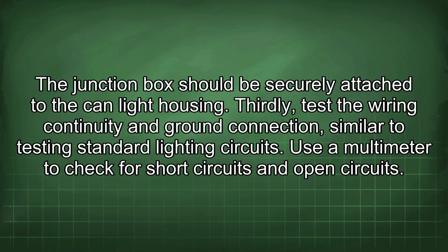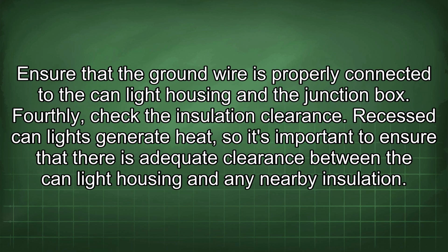Thirdly, test the wiring continuity and ground connection, similar to testing standard lighting circuits. Use a multimeter to check for short circuits and open circuits. Ensure that the ground wire is properly connected to the can light housing and the junction box. Fourthly, check the insulation clearance.